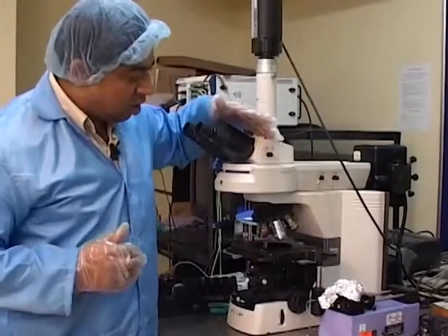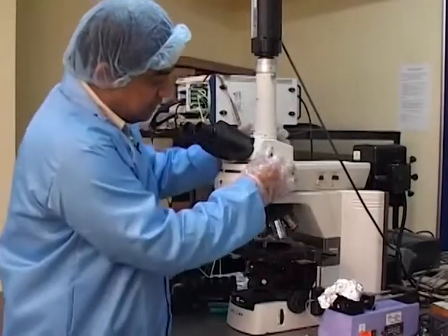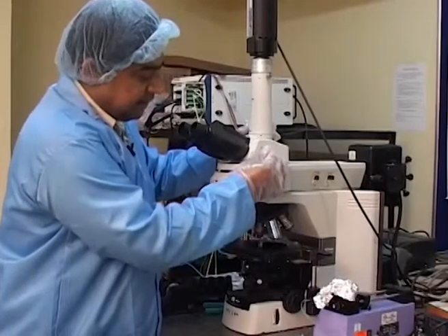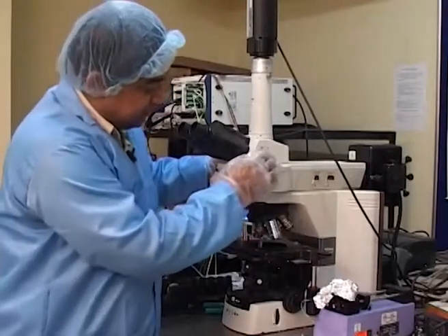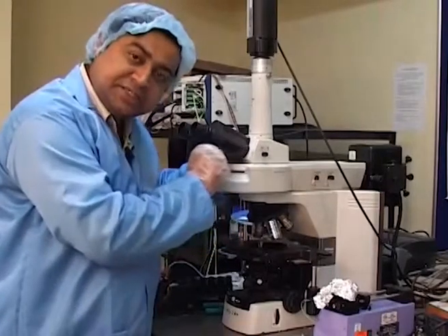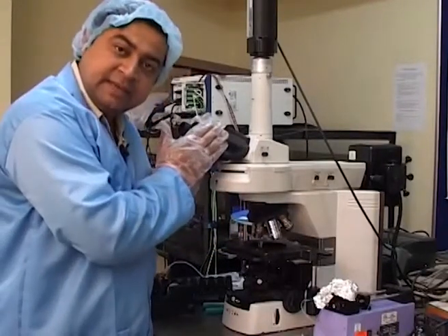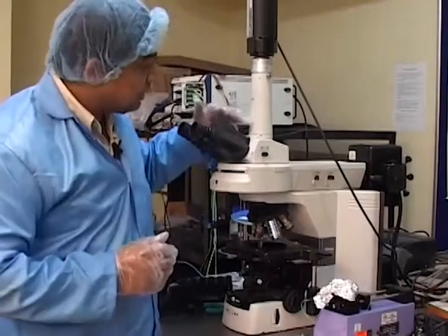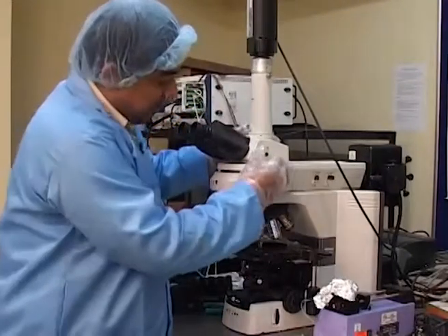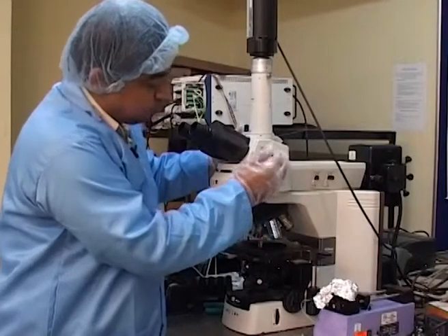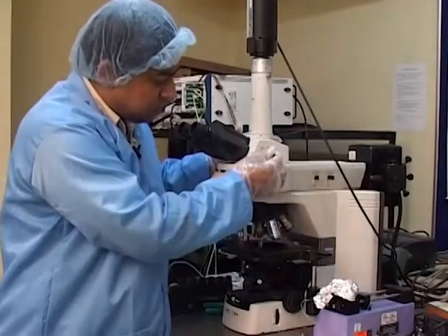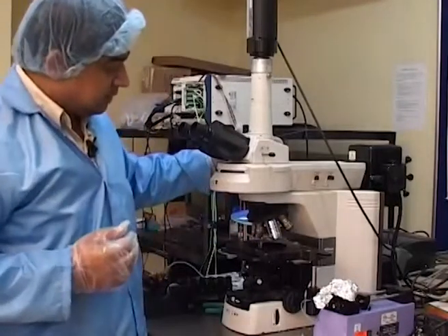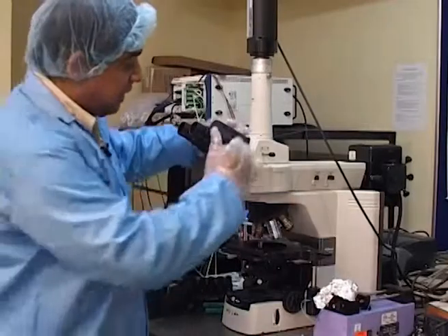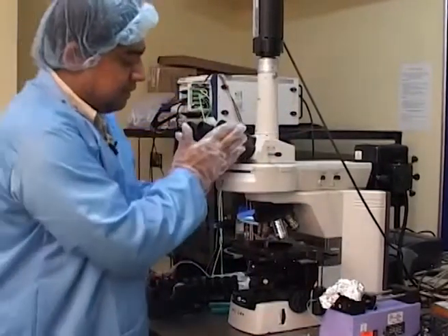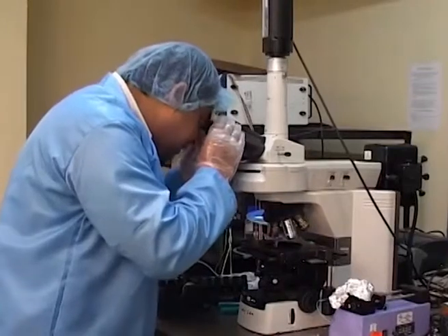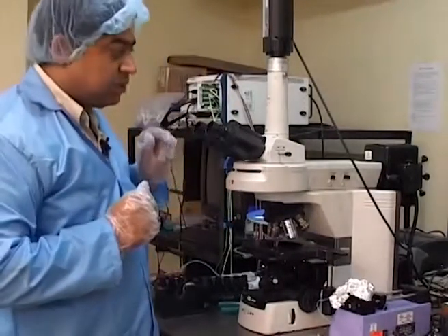Now, there are 3 options in this particular lever, as you can find out, and this lever can come out and go back in, right. So, when the lever is in its inward position, it only exposes the eyepiece and you can only see the image, but you cannot see it through the CCD camera. But if you push it all the way to the most outward position, in that position you can only expose the CCD camera and cut off the eyepiece. So, you cannot see anything by this eyepiece. So I am going to now transmit.